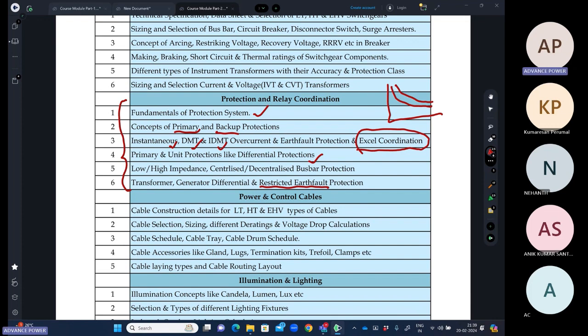So in this case, I will discuss the winding. You might have seen the concept somewhere that a fault happening at this point is of a different magnitude. A fault happening at this point will have a different magnitude. A fault at the mid of the winding will be of a different magnitude. A fault near the neutral will have a different magnitude.